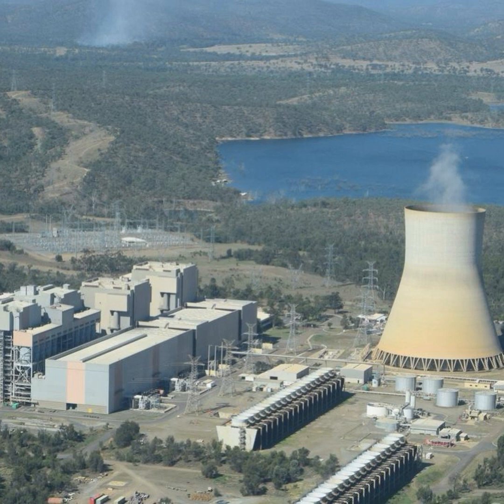Anyhow. The amount of energy able to perform work has traditionally been limited to about 33% overall energy conversion efficiency due to boilers and pipework material limitations. However, with recent material science advancements, operating at higher temperatures and pressures now makes it possible to exceed this. Several supercritical plants have achieved 44% overall efficiency in operation, with some experimental plants creeping up towards 50% efficiency. More efficient, less energy is wasted, seems like the way to go.